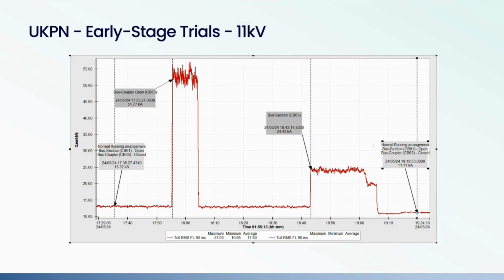And having closed the circuit breaker, the value increased to around 24, and that aligned much more closely with the partial transformer paralleling. In the later trace, there's also an interesting dip towards the later part of the graph. It shows a visible step change that also coincided with the reduction in the embedded generation.